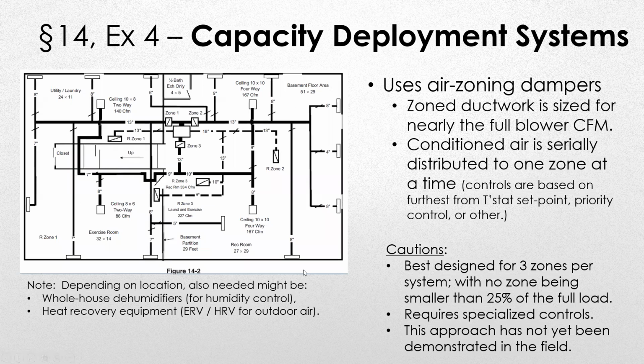The capacity deployment system, what is shown here, is basically a 3-zone system. If you have a home that has really good diversity, you can break it up into zones because, as we all know, each zone is going to peak at different times of the day. So for this system, in a capacity deployment system, if this were a 1-ton system and we had the requirement, we could break this up into 3 1-ton zones, and we only let one zone at a time be a caller. And there's no modulating of the other systems. So you could have up to a 1-ton load at a time.